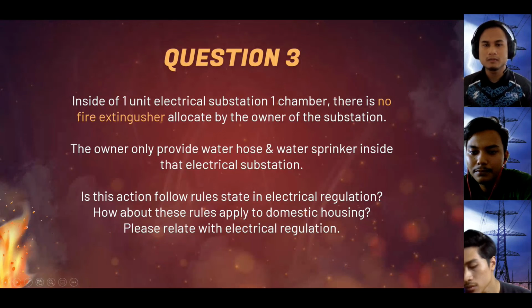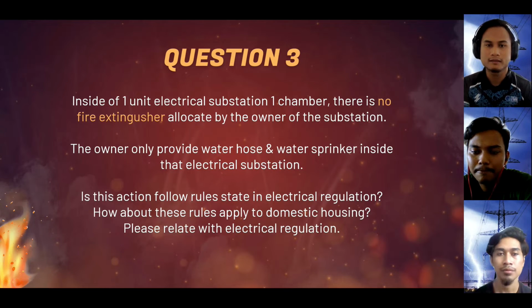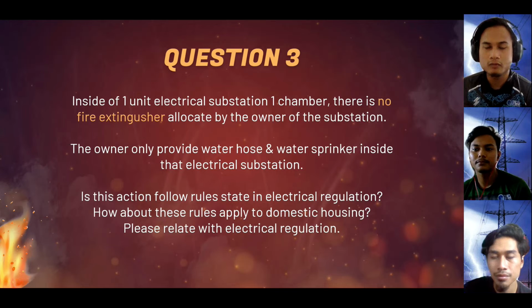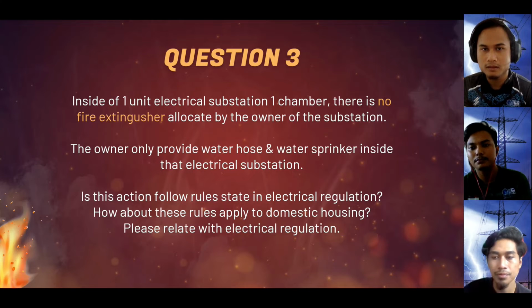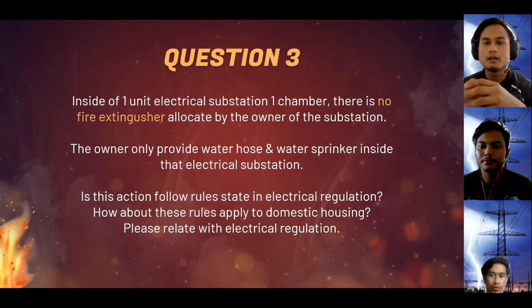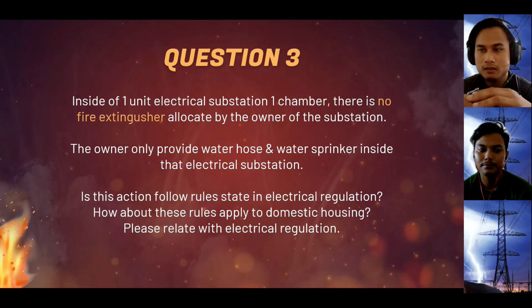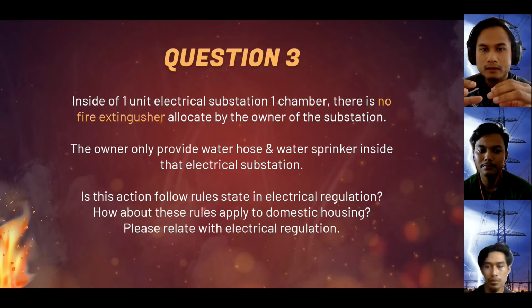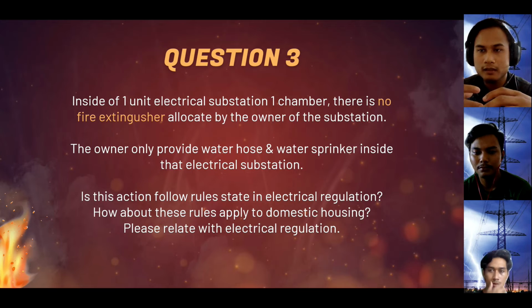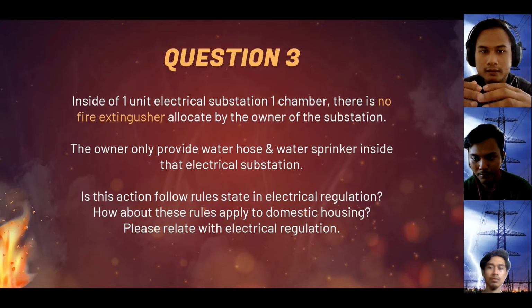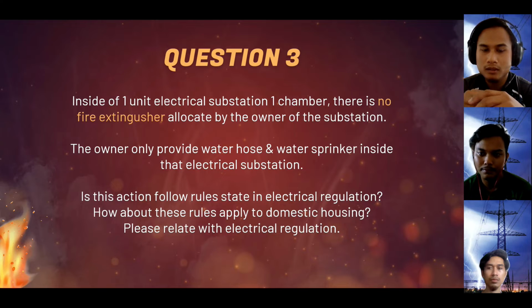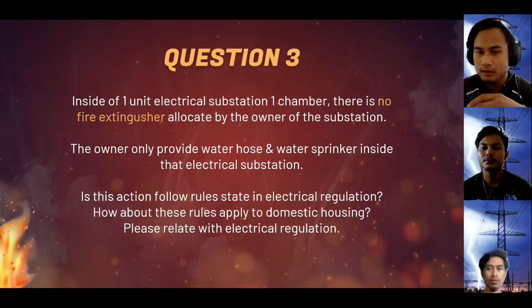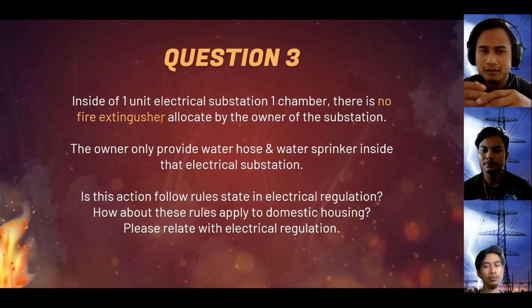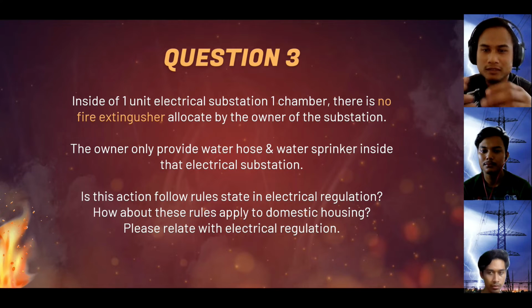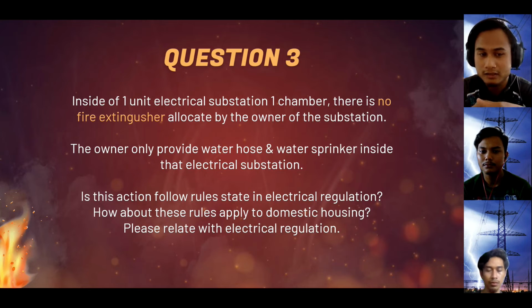The question we got is that inside one unit of an electrical substation, one chamber, there is no fire extinguisher allocated by the owner of the substation. The chamber, like a room, has many electrical appliances inside the substation. The owner only provides a water hose and water sprinkler. Is it enough for the owner to provide only a water hose and water sprinkler without a fire extinguisher?